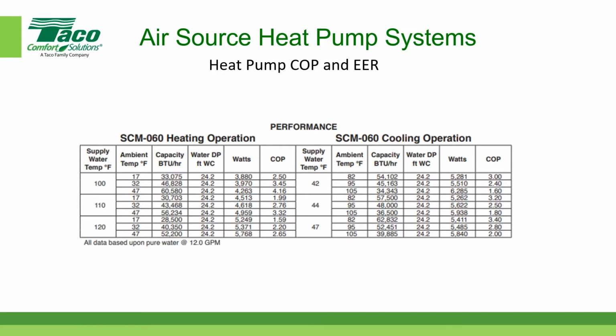Someone's asking, he lives in Fairbanks and he's wondering if you know of any air source heat pumps with a COP above 1 at -20. I'm not personally aware of equipment that has a COP above 1 at -20. I do know that there are several manufacturers that are experimenting with CO2 as a refrigerant. Some of the initial research and development indicates that they may be able to get COPs above 1 at relatively low temperatures. I'm not going to say that they can get above 1 at -20 degrees Fahrenheit.